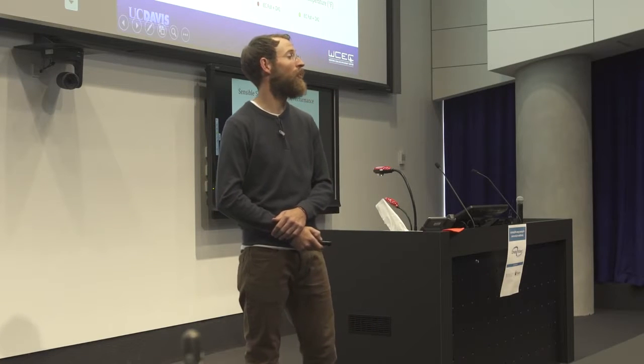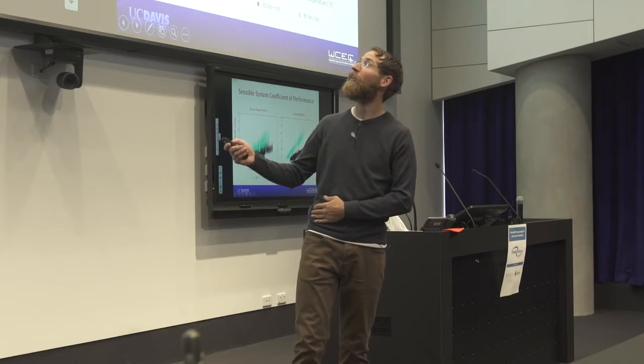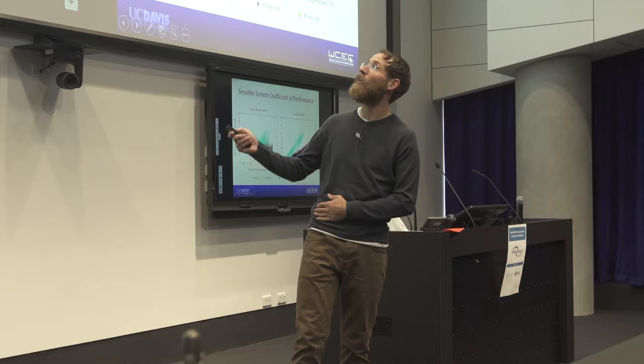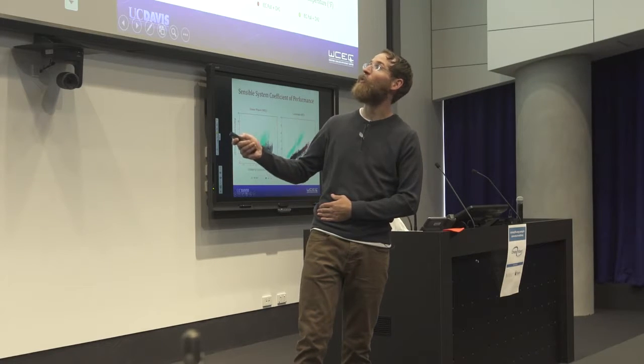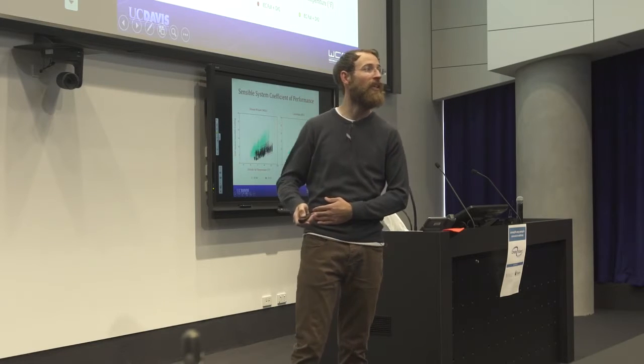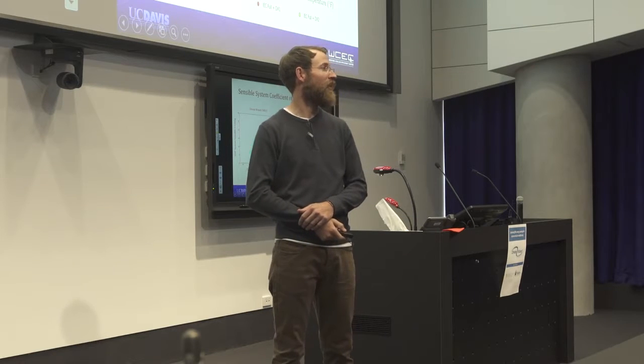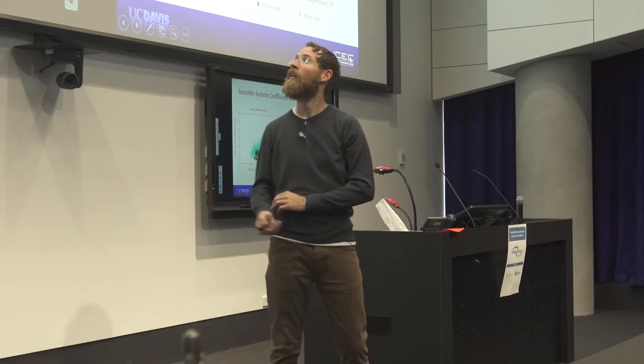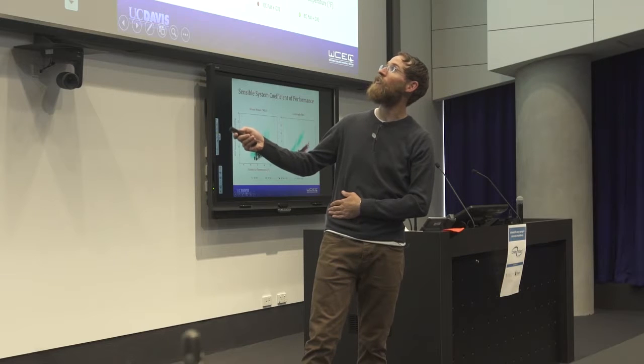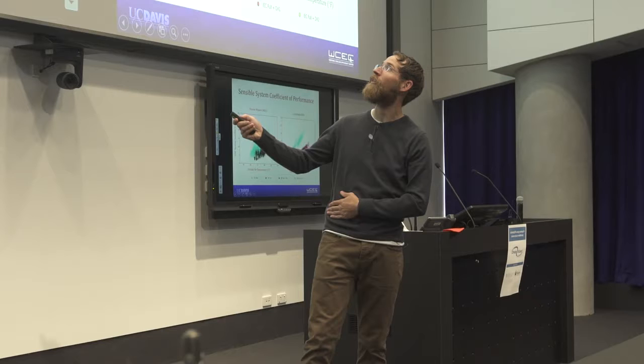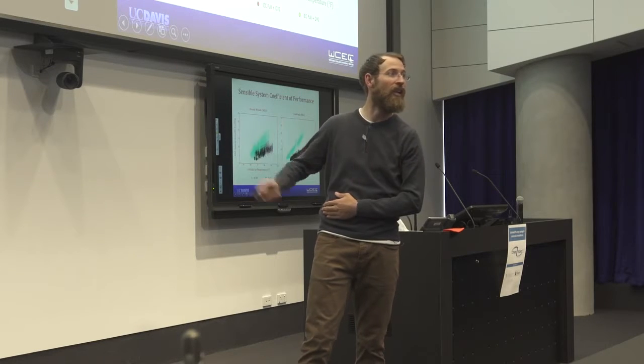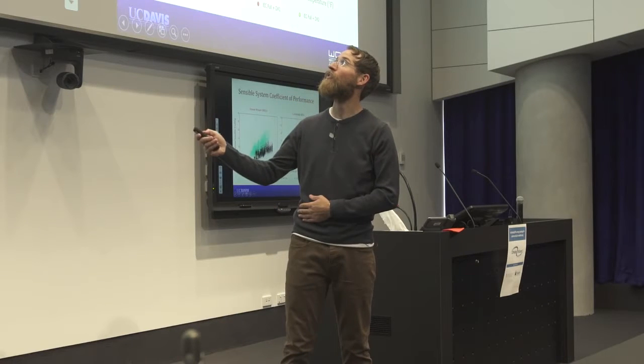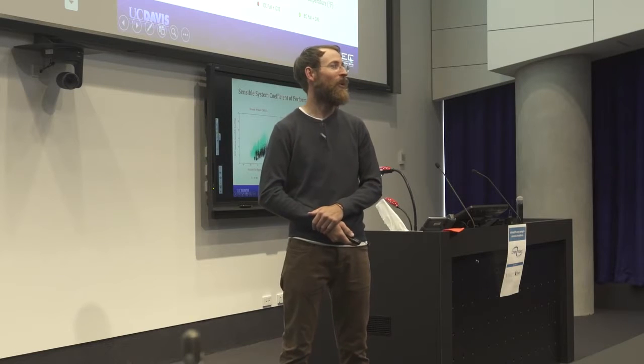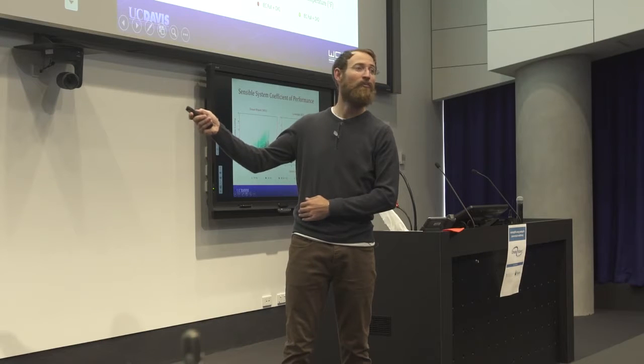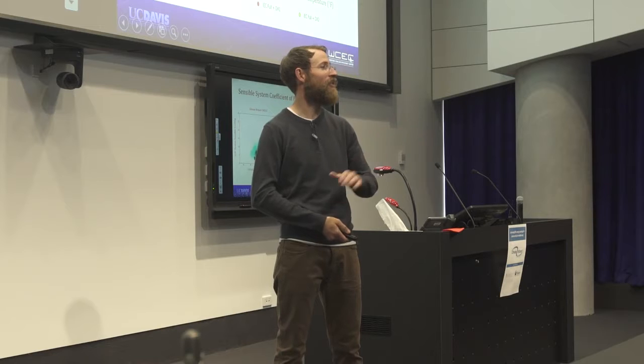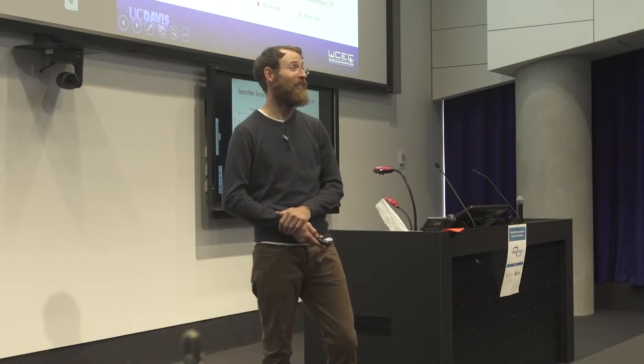And those two systems showed very similar COPs, coefficient of performance for cooling. The black dots here show all of the instances for operating in indirect evaporative cooling at full speed, and the light green dots show all the instances of COP for that observation period when it was running at part speed. In this case, we had controlled the system to two different speeds. And so here you can see at peak conditions of 100 degrees, you would be hitting a COP of about 15. And at part load here, when you're between 75 and 85 degrees Fahrenheit, middle range conditions, you can reach incredibly high coefficient of performance when running at part speed. And in these instances, part speed cooling operation was adequate to hold the conditions in the space without any additional compressor operation. It's really, really exciting to see.